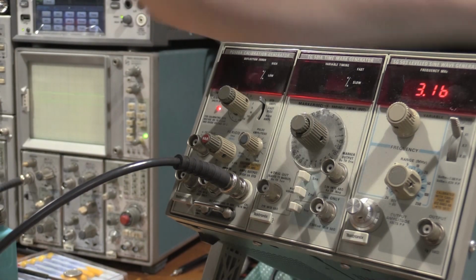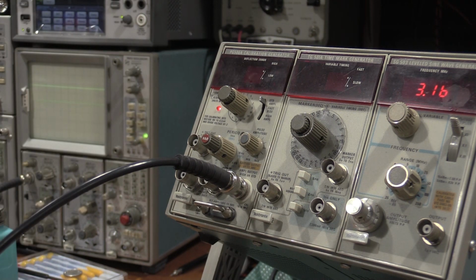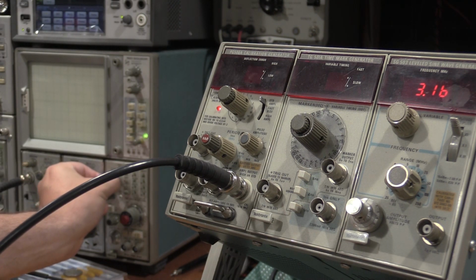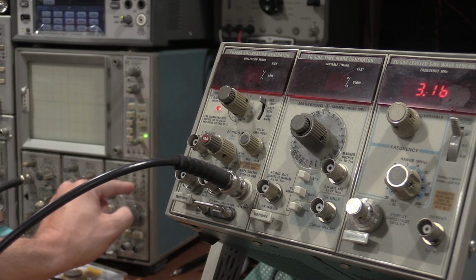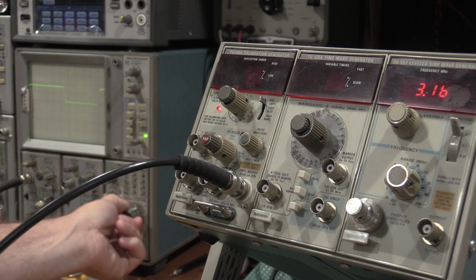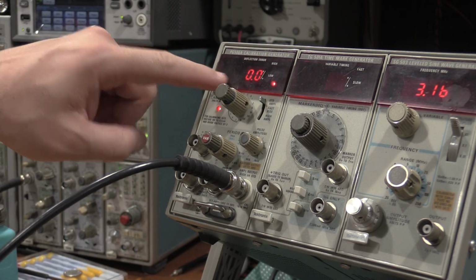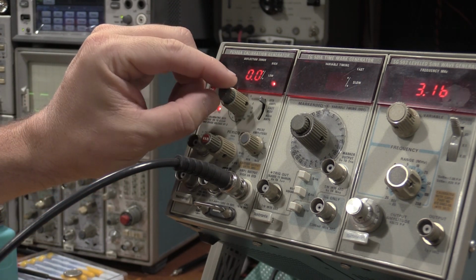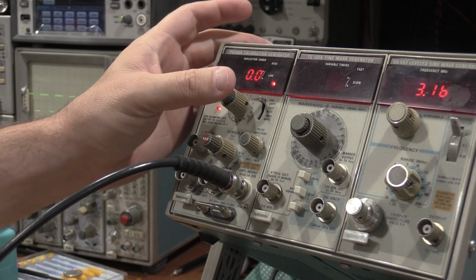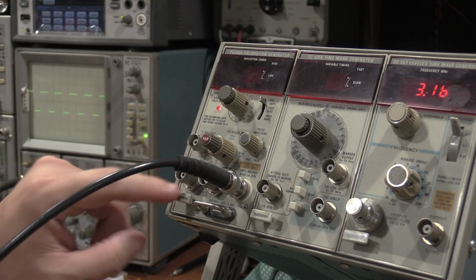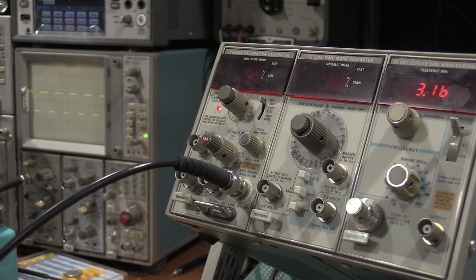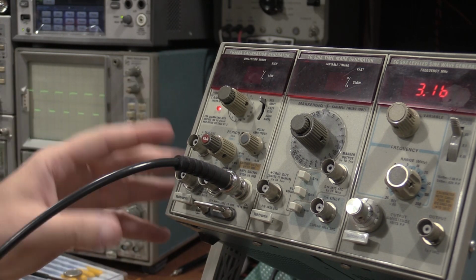Let's see. Okay, well, we have good... hey, look. We'll get this triggering here real quick. AC, high frequency reject. Slow this way down. Well, that's a problem. The deflection, or the error should be reading. So we have an error on the PG506. Well, that's not good. Something to troubleshoot. So we have our first fault.